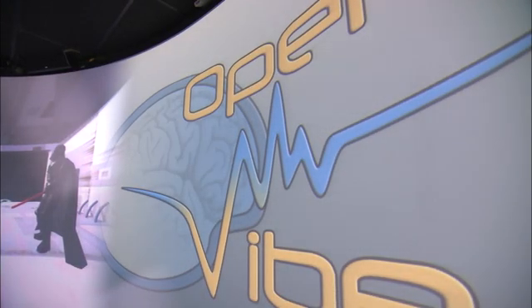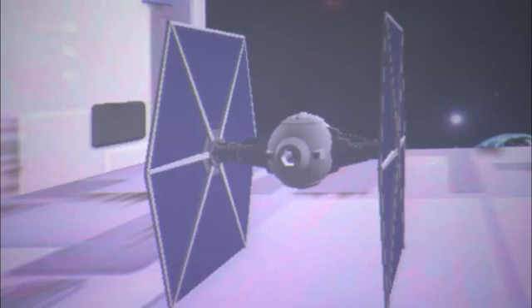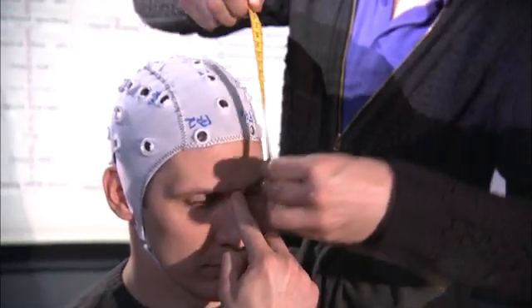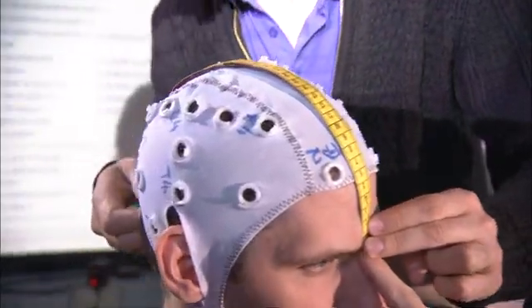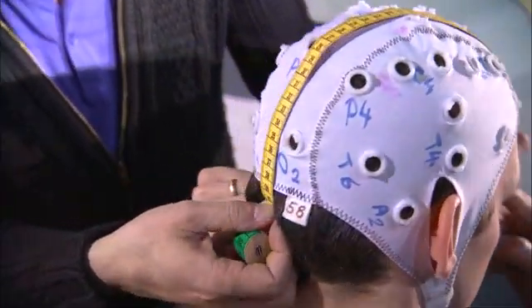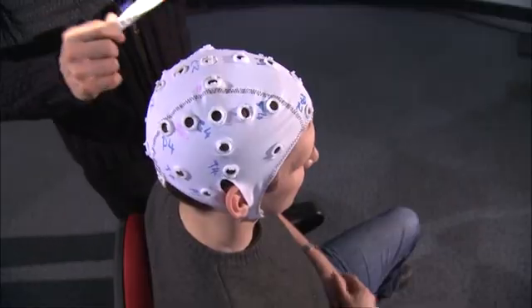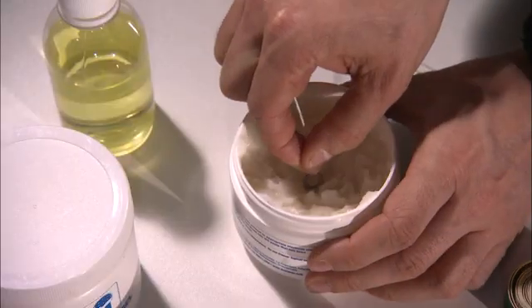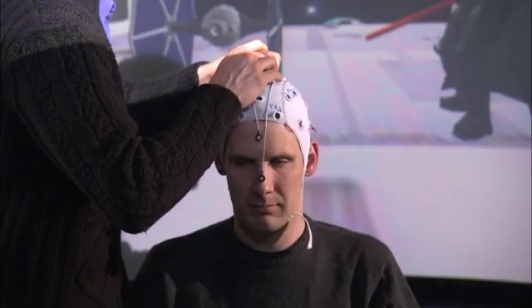To use a BCI under ideal conditions and allow a user to carry out commands using thought, the position of the EEG cap is crucial. In order to place the electrodes at the precise locations required for recognizing brain activity, some measurements are necessary, as for example here for the CZ electrode located on top of the head. Two electrodes are often necessary, one on the nose, the other on the forehead, corresponding to neutral and ground.